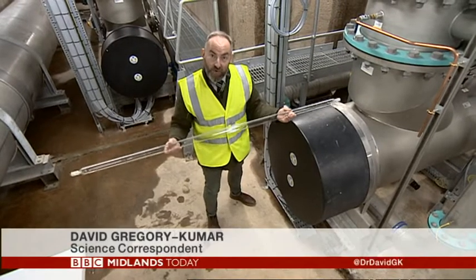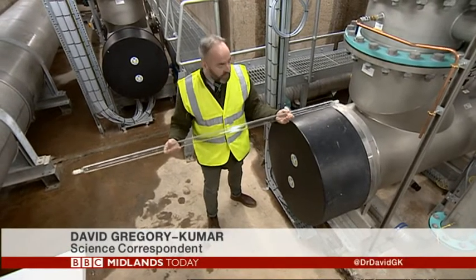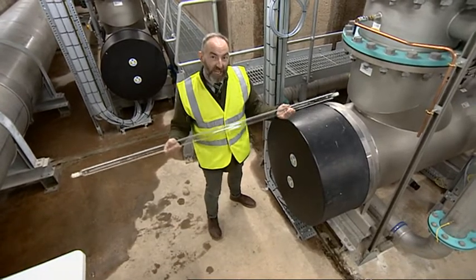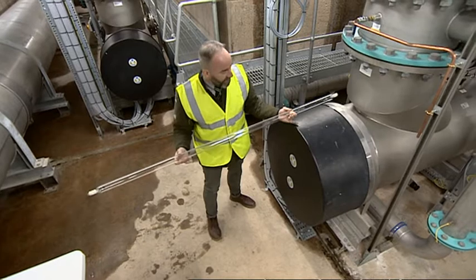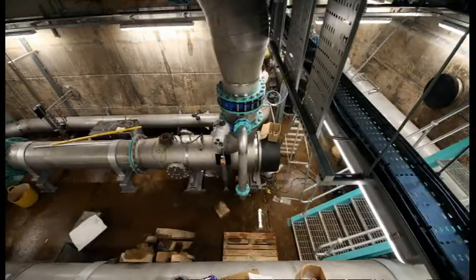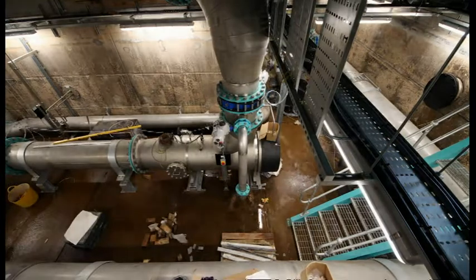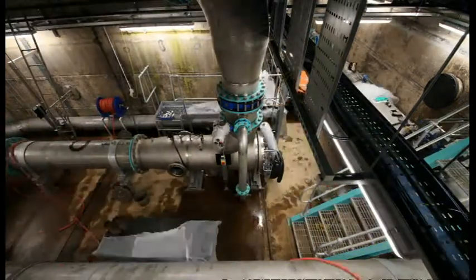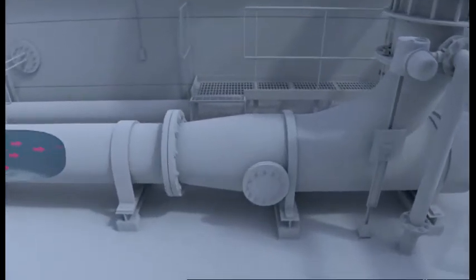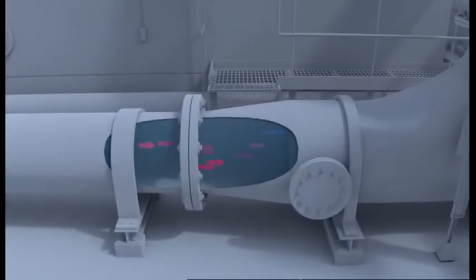This is one of the UV tubes that will be cleaning the water. It's worth about £250 and there are 30 in each UV reactor — that's this bit here with the big black cap. The UV tubes clean the water and allow South Staffs to reduce traditional chemical treatments like adding chlorine. Water flows over the ultraviolet lamps as the final stage of treatment before reaching customers.